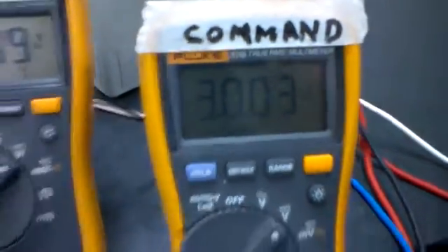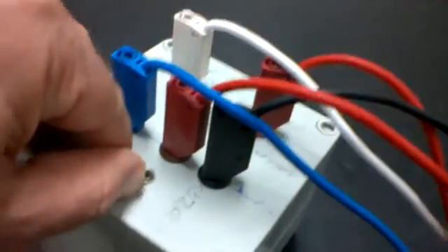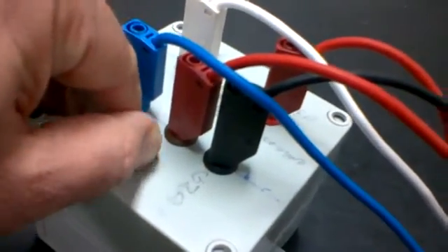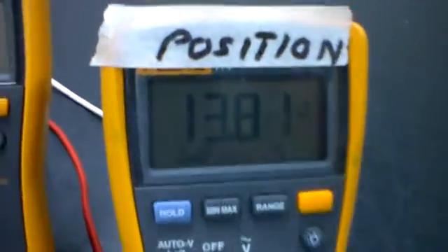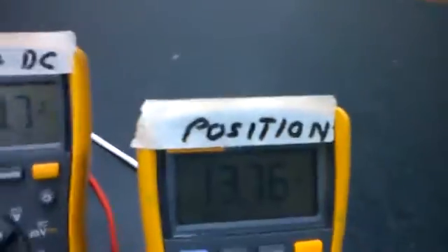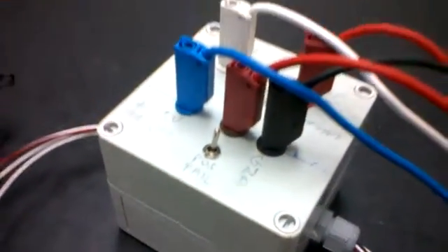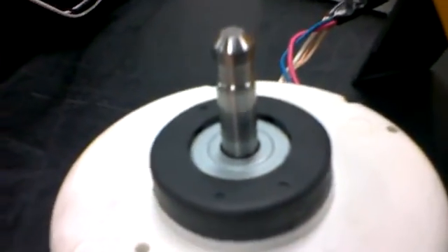Now I'm going to cause a position fail by shutting off this switch, and this switch will disconnect the position feedback sensor from the motor. If we have a look back here, you'll see it's locked up on about 13 volt. That's coming back from the motor itself, but it's being prevented from getting back to the PCB, because I have disabled it from this point here.